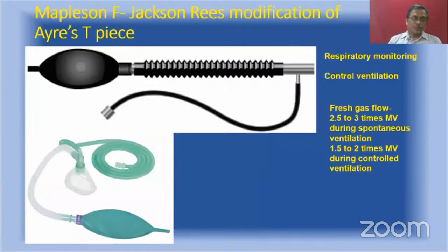See, this is a modern T-piece. You see here, this T-piece is metal in the older version, but here it is plastic. And the fresh gas inlet is longer, and the expiratory limb is also a little longer, with a reservoir bag with a hole in the tail. What's the function of the hole in the tail? It is acting like the expiratory valve. So during spontaneous breathing, you just keep that tail open, but during controlled ventilation, with the thumb, you have to occlude that tail partially to facilitate inspiration.